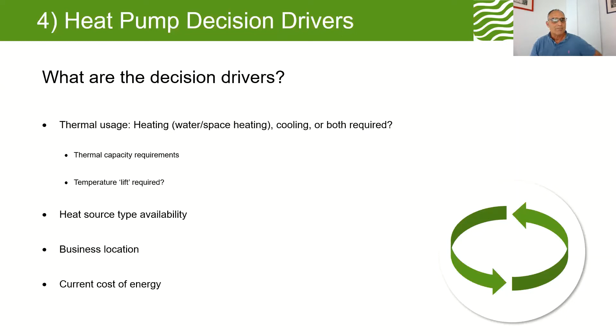So with regards to the costs, it's a good segue into considerations for return on investment, and some of the errors we try to prevent. As mentioned before, heat pumps work vastly different than a gas boiler, and their coefficient of performance is very different. Therefore, we do not size for the peak loads, but more for the average usage, which prevents unnecessary capex - initial outlay of capital - and also the underutilization of the heat pump.